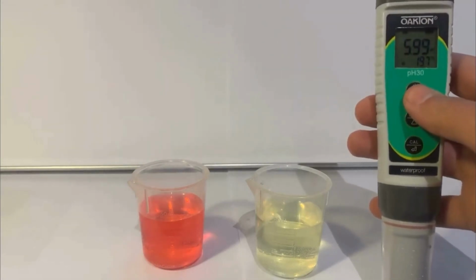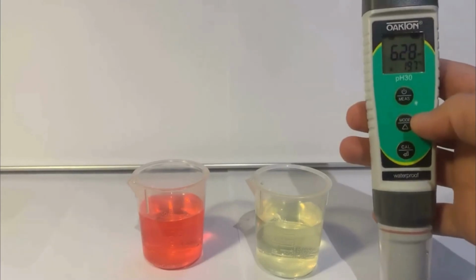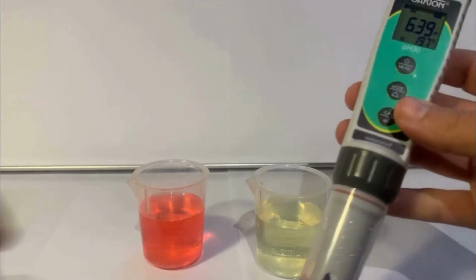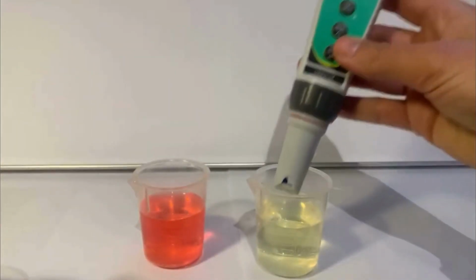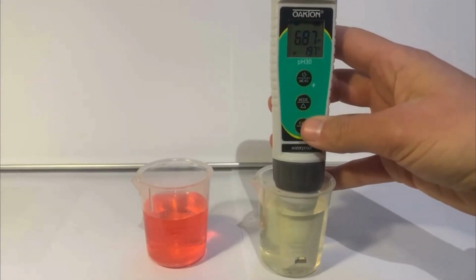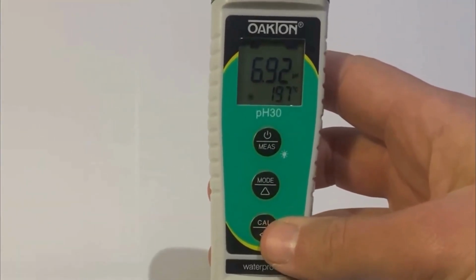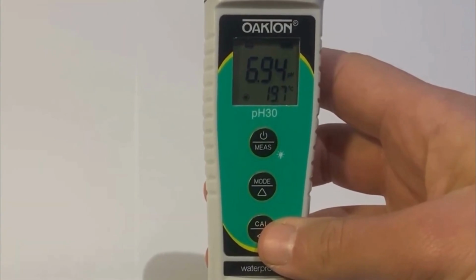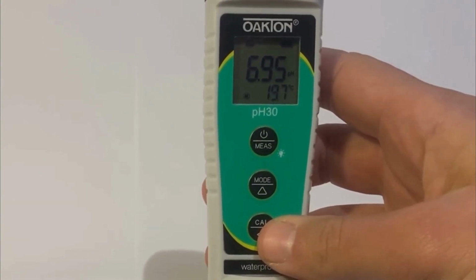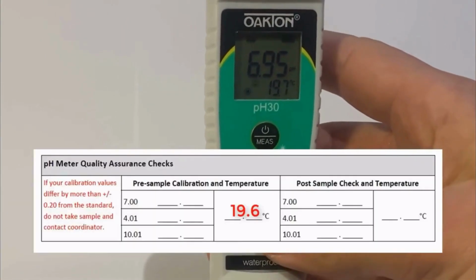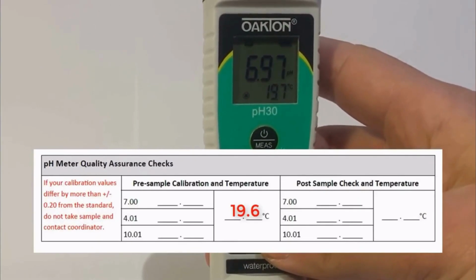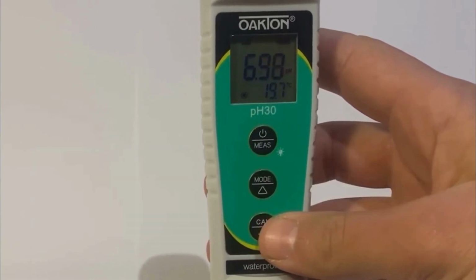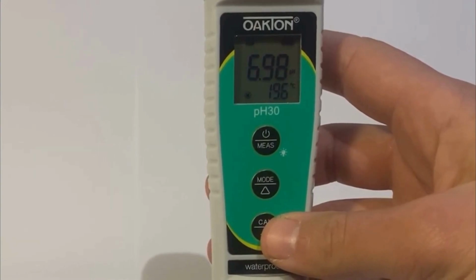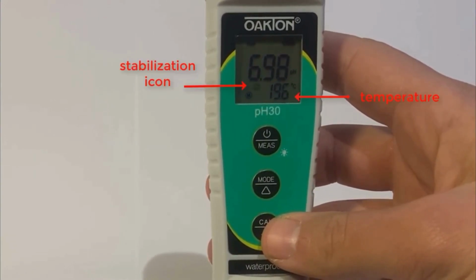Always start with your Buffer 7 solution. Place your meter into the yellow cup and wait for the stabilization icon, which is the small smiley face, to appear. Once it appears, record your temperature, which is the bottom number on your datasheet. The top number is what your meter is currently reading. This will most likely be very close to 7, but not exact.